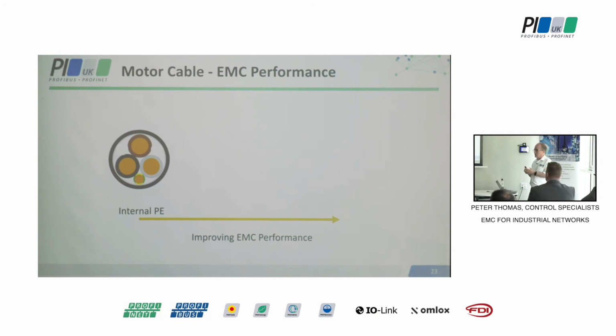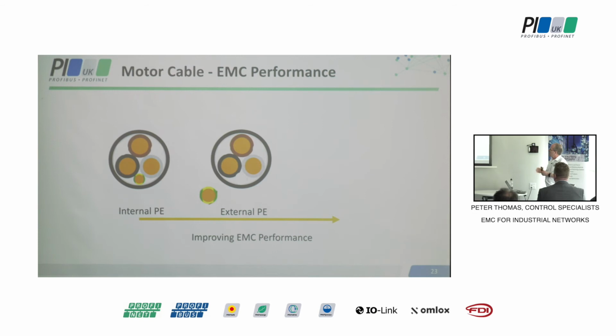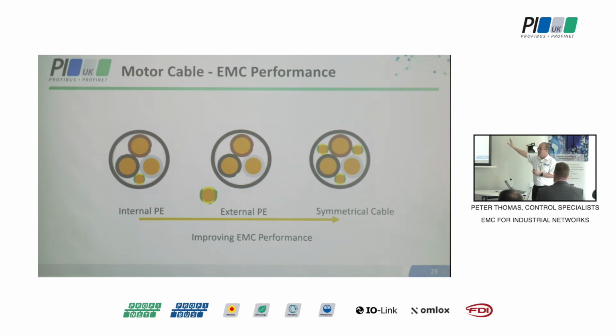Okay, so what about the cable? What can we use with the cable? Well, it seems to vary. Some people just put three-phase cable with some armouring because it was three-phase in, it's three-phase out. Some people have a cable with an internal PE. Some people decide to take the PE, the protective earth, outside of the cable. But the recommendations now are that you're more likely to get an EMC compliant installation with symmetrical motor cable. Paul from Belcom is in there somewhere, and he was telling me they're getting more and more inquiries for this cable. It seems that the message about EMC issues is getting around.